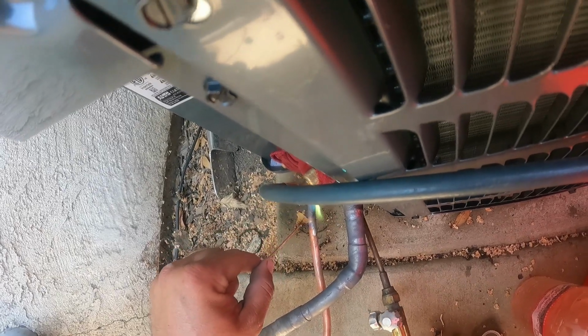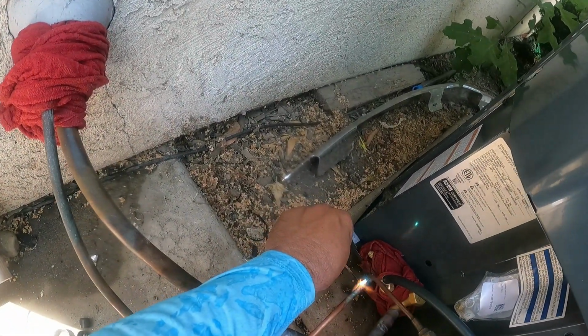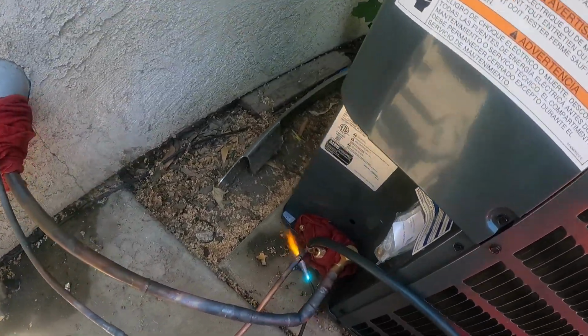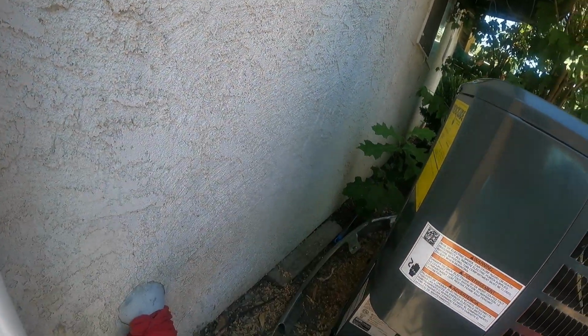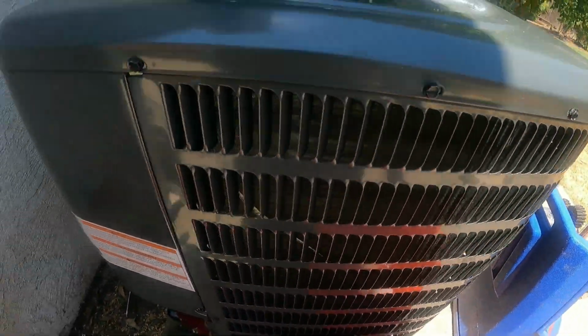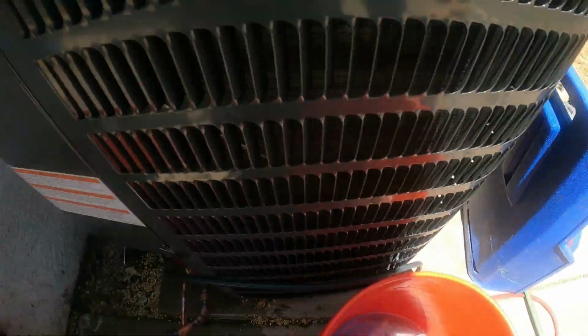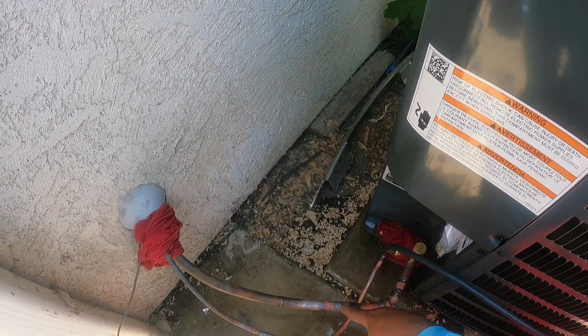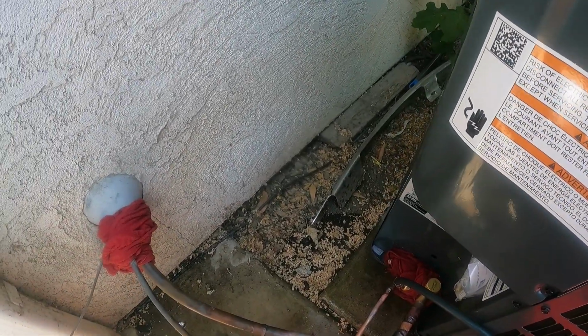Oh, that wasn't too good. There we go. There we go. That's mostly done, folks. Boom. Now make sure to cool your welds off pretty quickly. And then I'm gonna go back, sand it and clean it, and then I'm gonna finish welding the bottoms. But you see, I didn't even use one full piece. And I did 1, 2, 3, 4, 5, 6, 7, 8 connections. Removed the schrader valves, nitrogen braze, clean work.